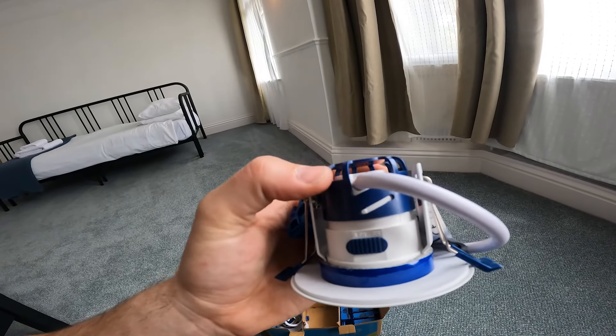The downlight has loads of features. You've got the pop-up hood, so if room was an issue and they want insulation above, you could slide it down and it would still squeeze in - but if you wanted airflow, you'd pop it up. The click flow leads are cool, and it's a push terminal now rather than a screwdriver. That's miles better. We also had the colour temperature and wattage options - if you wanted a dimmer light level you put it on 4 watt, or bang it up to 6.4 watt for a lot brighter. You can change the colour between warm white, cool white, and daylight. And they're also dimmable and you can put them in the bathroom - it's an all-rounder light.